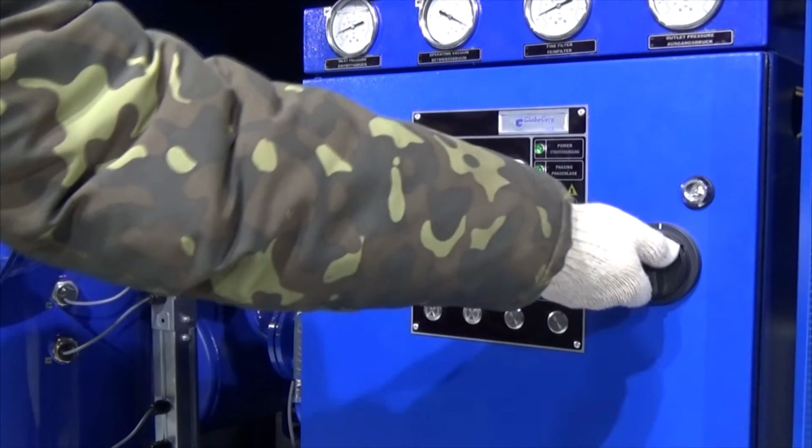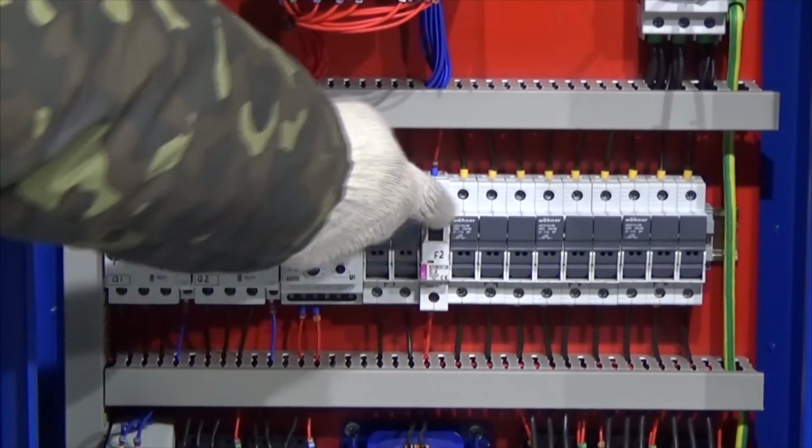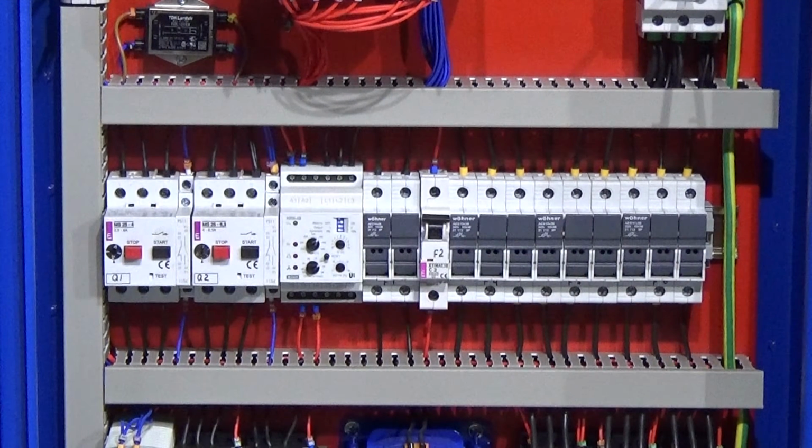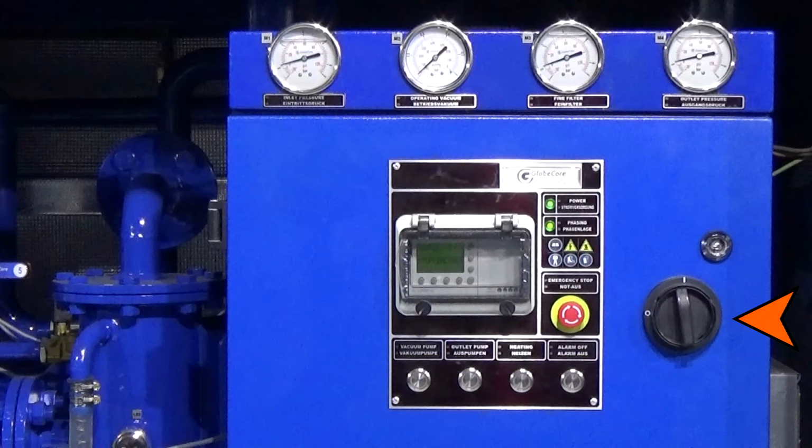Open the control cabinet. Connect power to the unit using a 4-wire cable. Turn on automatic switch F2. Close the control cabinet. Turn the power handle on the control cabinet to the on position. Correct phasing is indicated by the green light on the phase control relay and the phasing light on the front panel of the control cabinet. If the power light is on while the phasing light is not, check phase control relay settings and, if necessary, swap connections of phases on the input terminals of the phase connector. Turn the power connector handle on to the on position.